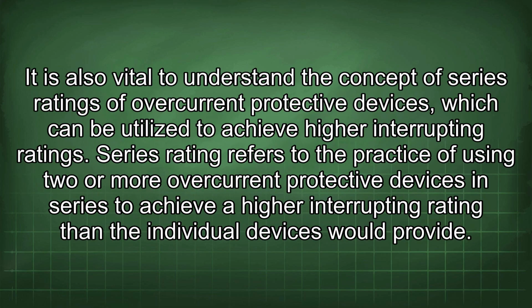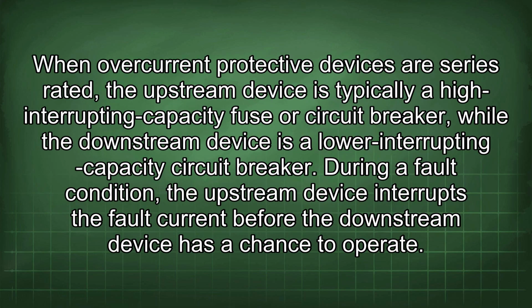It is also vital to understand the concept of series ratings of overcurrent protective devices, which can be utilized to achieve higher interrupting ratings. Series rating refers to the practice of using two or more overcurrent protective devices in series to achieve a higher interrupting rating than the individual devices would provide. When overcurrent protective devices are series rated, the upstream device is typically a high interrupting capacity fuse or circuit breaker, while the downstream device is a lower interrupting capacity circuit breaker.